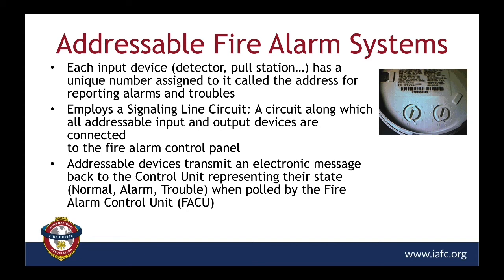They're going to use a term called signaling line circuit. That just means the pair of wires that all of these devices are connected to. In some cases we could have 30 to 60 devices on a pair. Some designs allow up to 250 or more devices on a pair of wires. That gets into some engineering stuff, which we're not going to touch on today, but a pair of wires can handle many, many addresses. Let's go to the next slide, Chief.